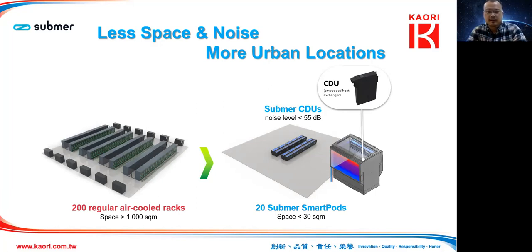In the picture on the left, you see a scenario for 200 regular air cool racks. The same computing power could be achieved by just using 20 Submer smart pods, and you will see a lot of space saved and a lot of equipment not needed. Also, if you use immersion cooling technology, the noise level for a data center or computer room could be reduced to less than 55 decibels.